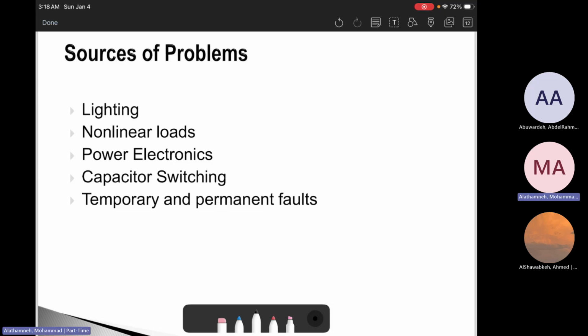Now, the mindset that you need to keep in your mind: power quality is not solved by one magic device. You can solve it by identifying the dominant phenomenon or the source and matching the mitigation to the cause. For example, if the source of the power quality problem is lightning, then make a surge protection, make a UPS, all right, ride-through capability. If it is harmonics, make a filtering. If it is grounding, make the grounding improvements. If it is a weak network, make the network strengthening. If it's an operational change, try to redesign the loads, redesign the system, and make voltage regulation to solve this problem. So understanding the source is half of the solution. Once you understand what's the main reason, then you just apply the solution.